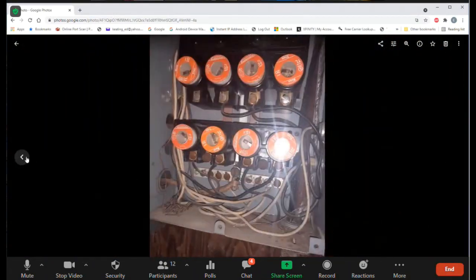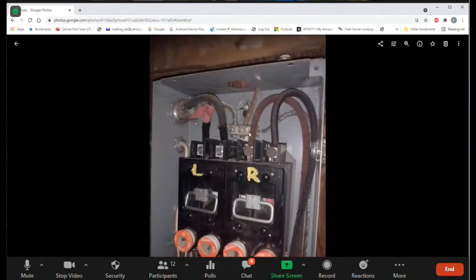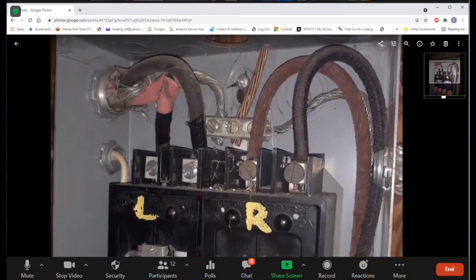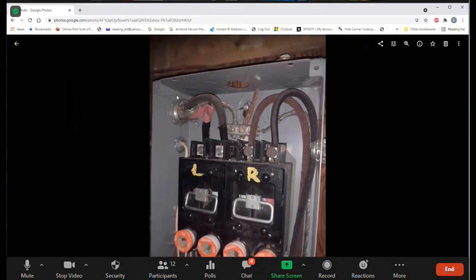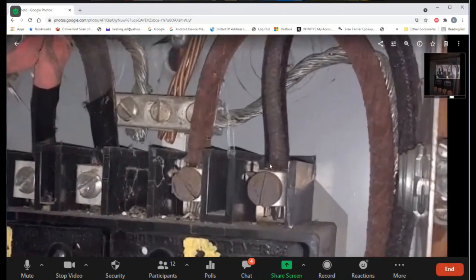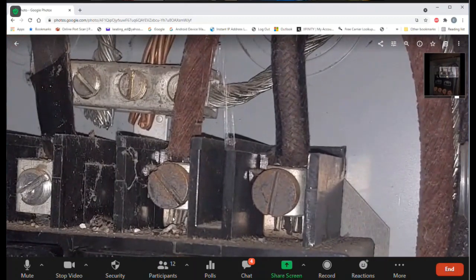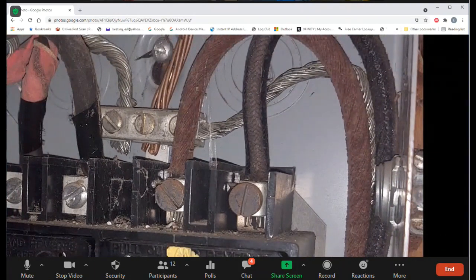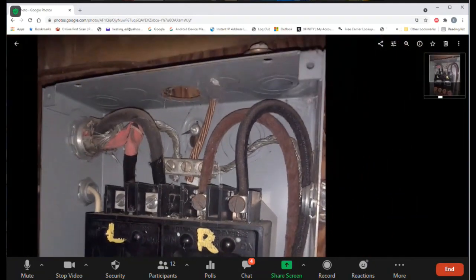Let's go back this way. There's another picture of the one flying. There's the top, you can see the ground and the 2 neutral cables that are ground cables coming in from the power line. Is that aluminum wiring? No, I think it's just tinned copper. Although it could have been aluminum, the main, I'm not sure if the main... let's see, can I see the main? The main is aluminum, but that's good for feeder cable. Feeder cable can be aluminum. And typically in your house right now, you probably do have aluminum coming in, at least to the meter, maybe not between the meter and your panel, but almost all of the service wiring coming into your house now has been aluminum for years. But as long as it's in an aluminum-certified connector, you're good.